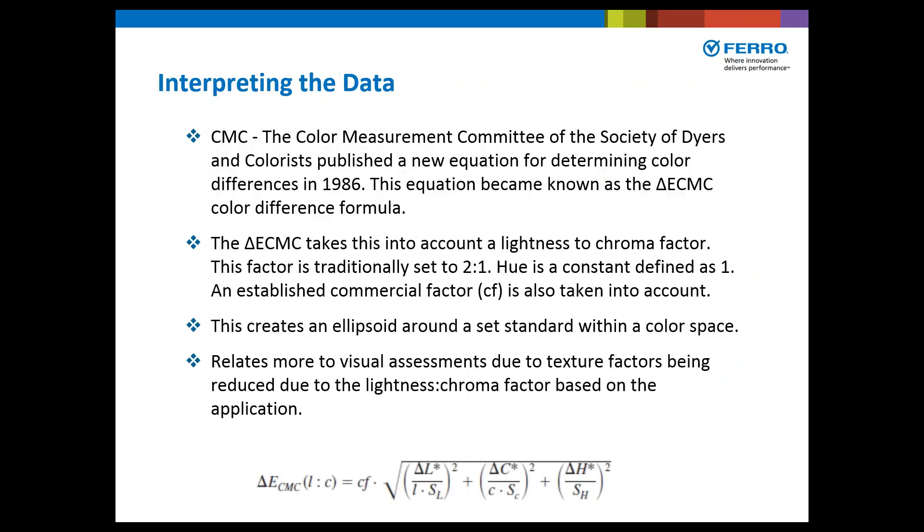In 1986, an additional formulation was developed by the Color Measurement Committee of the Society of Dyers and Colorists to help determine a more consistent representation of color difference. The delta E CMC takes into account a lightness-to-chroma factor, traditionally set 2 to 1; Hue is a constant defined as 1; and an established commercial factor, or CF, is also taken into account. This creates an ellipsoid around a set standard within a color space, relating more to visual assessment. Modern spectrophotometers and colorimeters calculate this formula automatically.